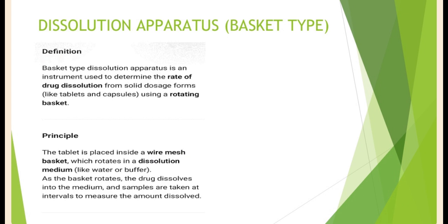Principle of basket type dissolution apparatus. The tablet is placed inside a wire mesh basket which rotates in a dissolution medium like water or buffer.